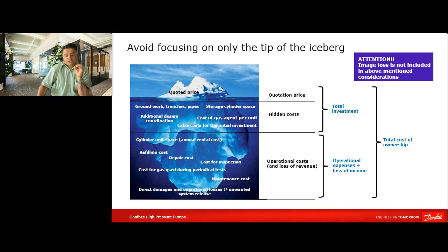But the total cost of ownership is not only limited to the total investment. You also have operational expenses, running costs day by day. And you also have to consider all those hidden costs, or the costs that you might not have seen in the beginning. Once you have purchased the gas extinguishing system and installed it, already in the design phase you have to consider conditions about the groundworks, about the trenches and pipes. You have to know that it is a high pressure agent, and then all those ceilings and the sealing or insulating of those rooms. These are the architectural efforts, those openings. And you might have the initial testing, which is testing of those cylinders inside those rooms and the refilling costs.